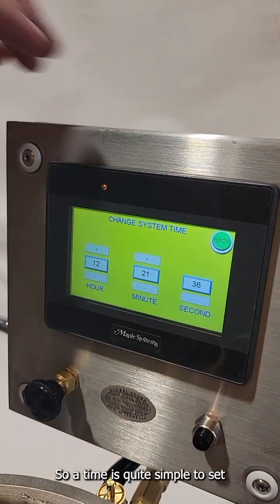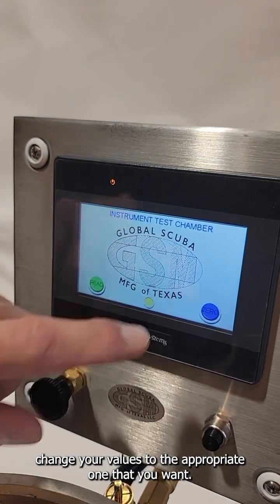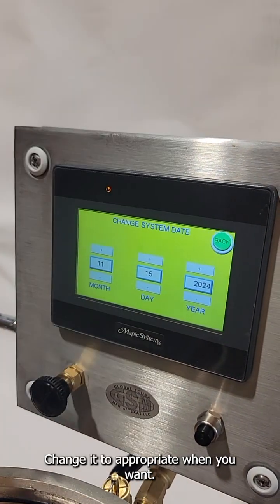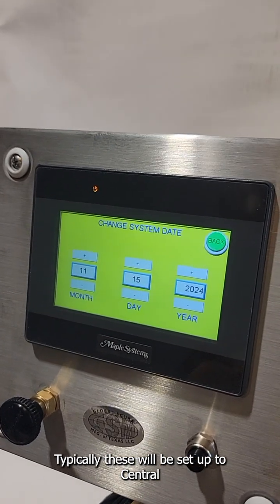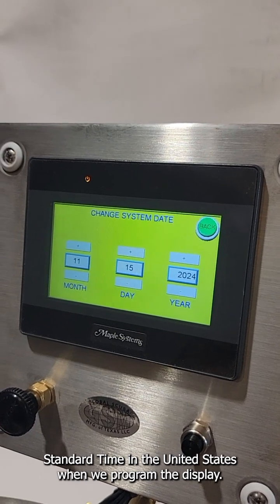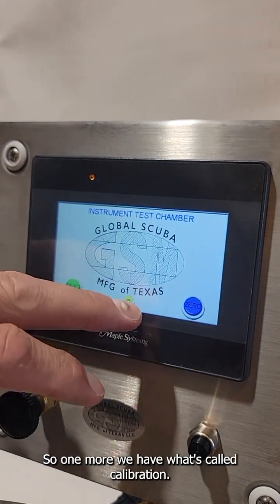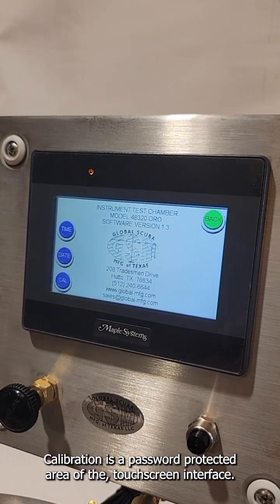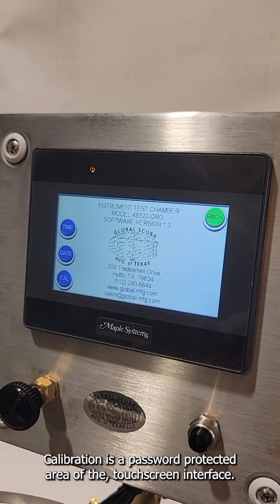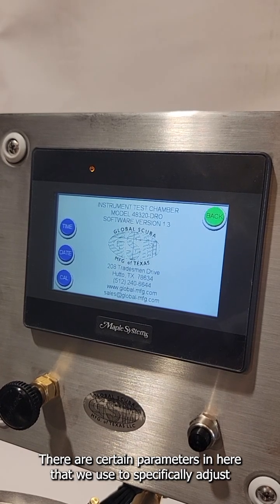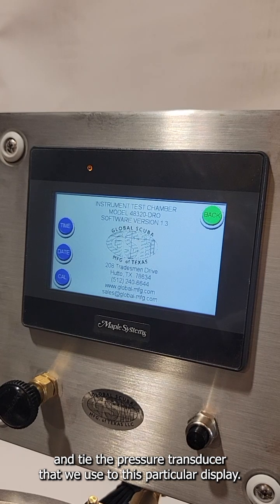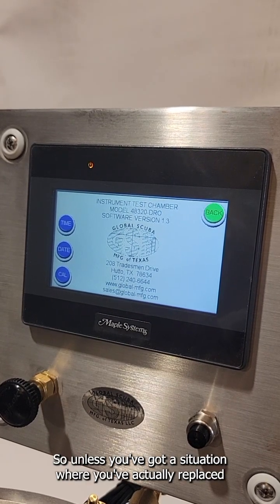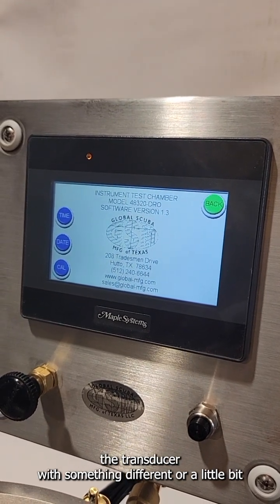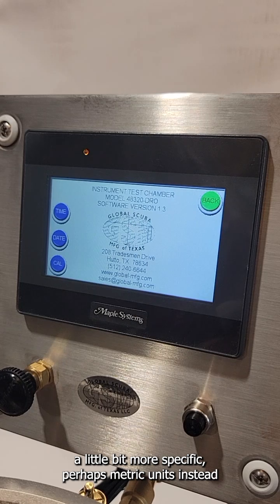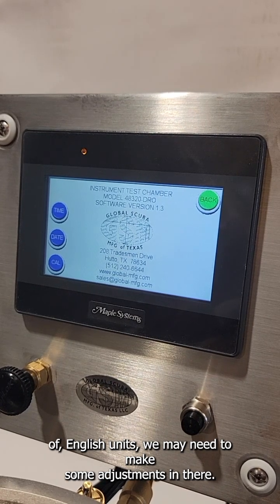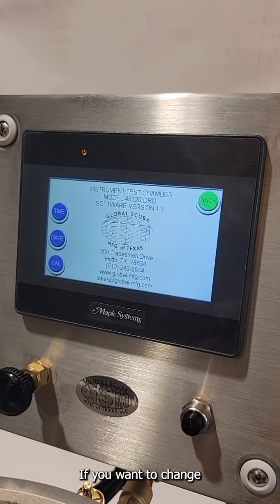Time is quite simple to set. Change your values to the appropriate ones that you want. Date, similar thing. Typically these will be set to Central Standard Time in the United States when we program the display. You may need to change it for your particular time zone. One more, we have what's called calibration. Calibration is a password protected area of the touchscreen interface. There are certain parameters in here that we use to specifically adjust and tie the pressure transducer that we use to this particular display. So unless you've replaced the transducer with something different, or need something more specific, perhaps metric units instead of English units, we may need to make some adjustments in there, but that is something you have to work with us at the factory on if you want to change.